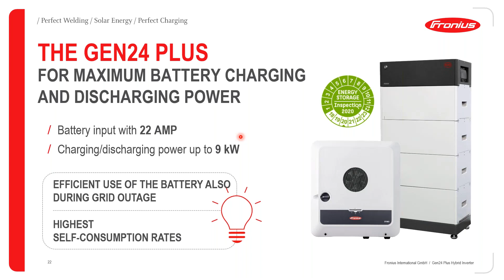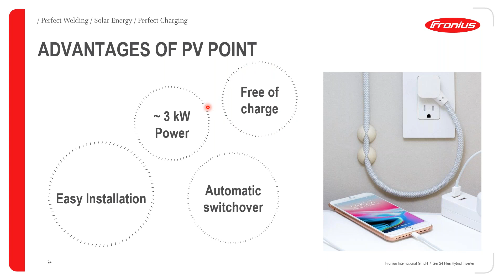Another unique feature that is embedded within the Gen24 Plus inverter is the PV Point. The PV Point, in a nutshell, is a connection for backup power that you can use even without a battery storage. So it provides you with a maximum of 3 kilowatts of power in single phase. The installation process is very simple, so you do not need to do isolation. And then the switchover, once there is a power cut, is automatic. And of course, like I said, you do not need to pay any extra fees to have the PV Point activated within the Gen24 Plus inverter. So it comes as an embedded feature for all the Gen24 Plus inverters.